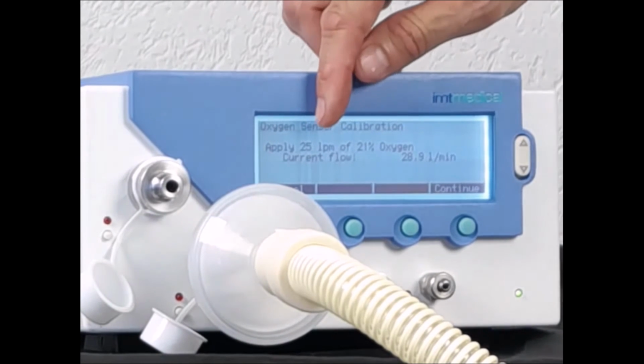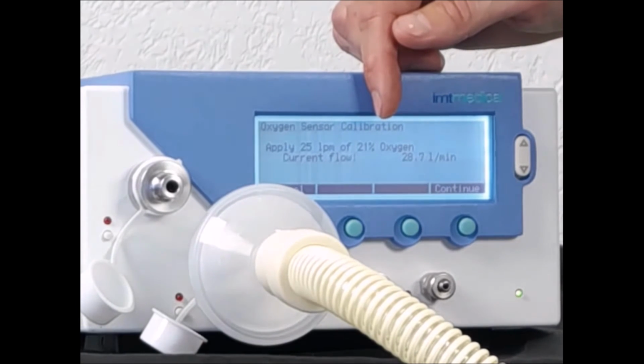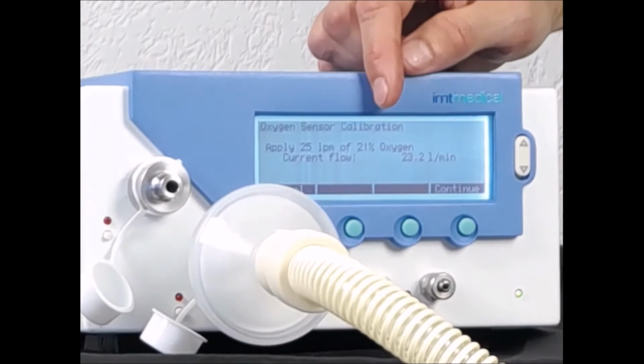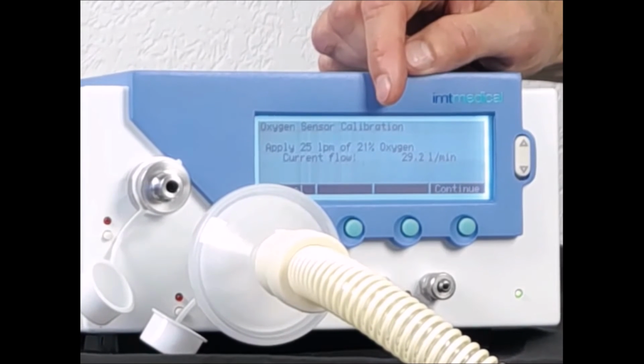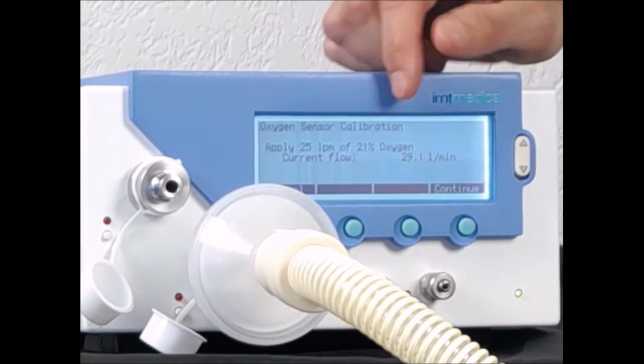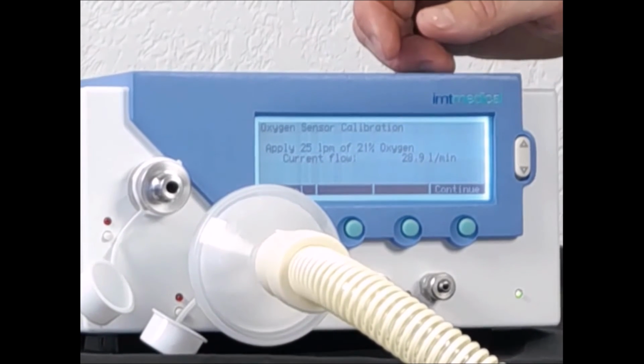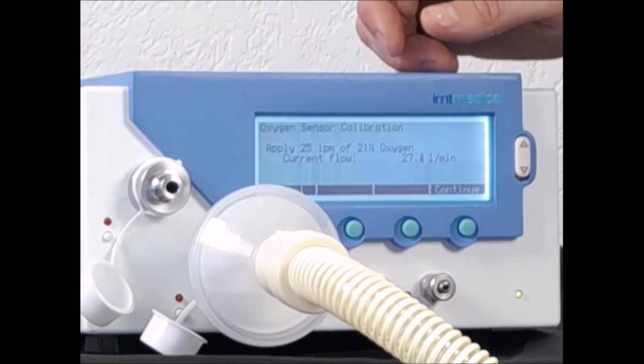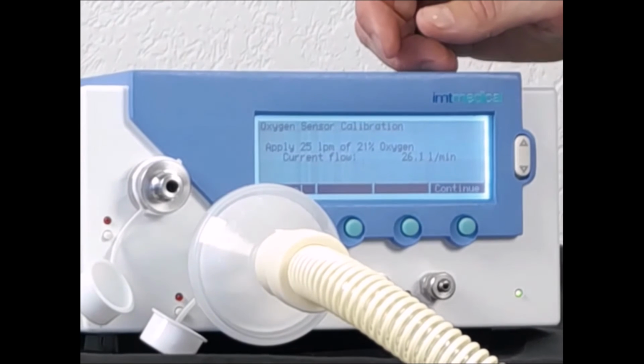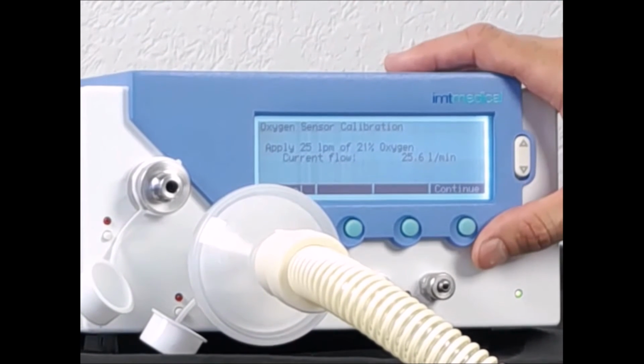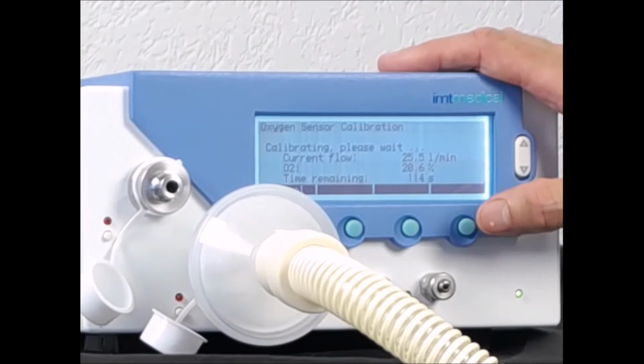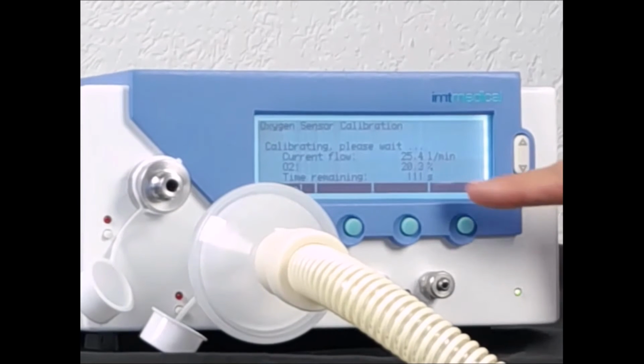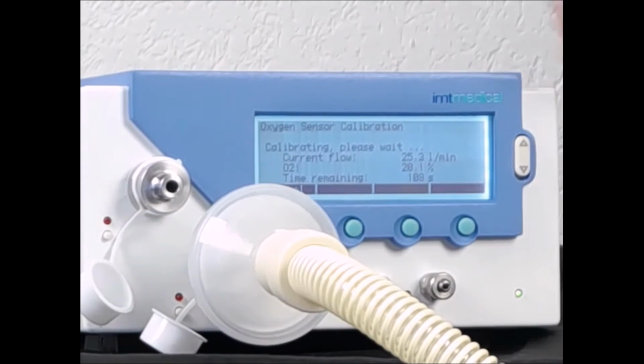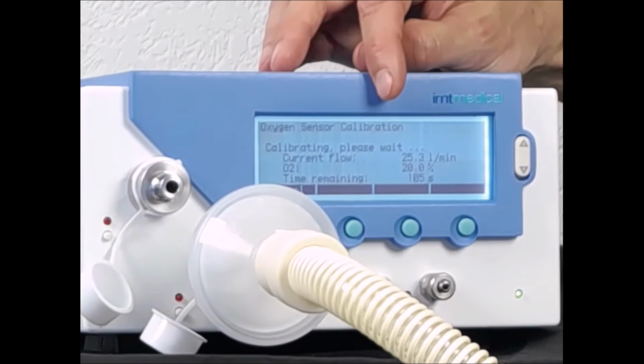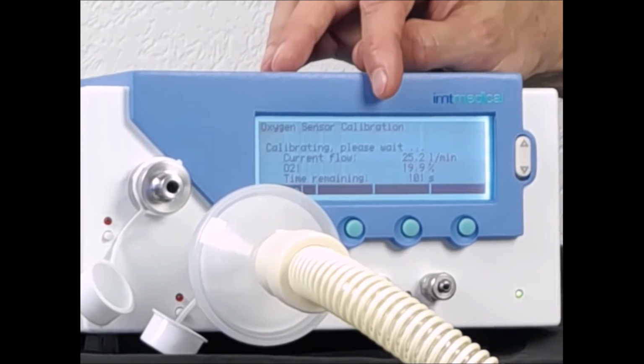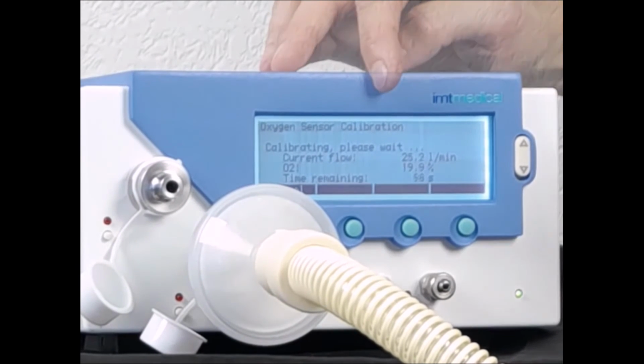So it tells me to apply 25 liters per minute of air. So again, I use the service controller of my ventilator to blow air through. I have now 29 liters, so I can fine-tune that a little bit to about 25. If I'm happy, I start the 21% point of oxygen calibration. Again, it will take me 2 minutes. I would like to repeat, this process, which takes a while, is only required once a week or ahead of very important oxygen measurements.